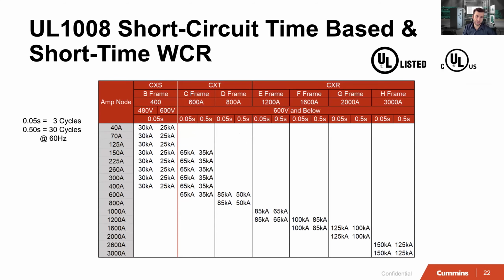And when we talk about the highest WCR, or withstand and closing rating, there's just a list of the numbers in here. For example, when we say the transfer switch, that's a 3000 amp, can handle 125,000 amps of fault current at 600 volts or below. That means we can run 125,000 amps for up to half a second. So if you have that downstream of a switchgear, it allows downstream circuit breakers to clear a fault.